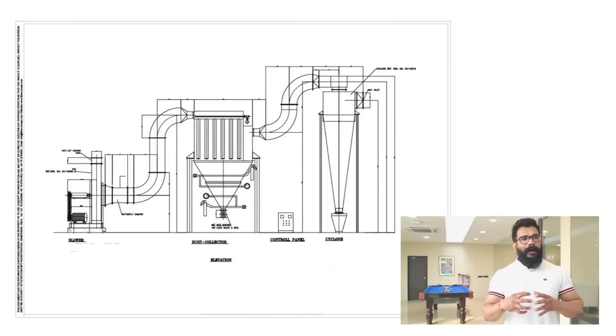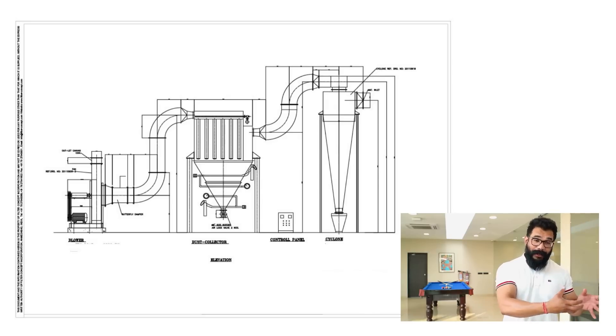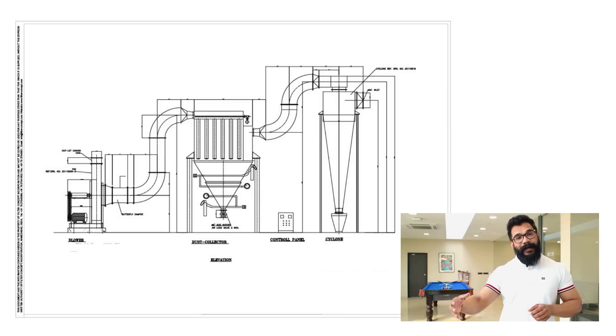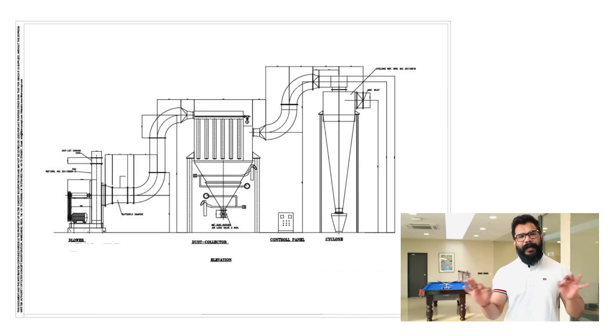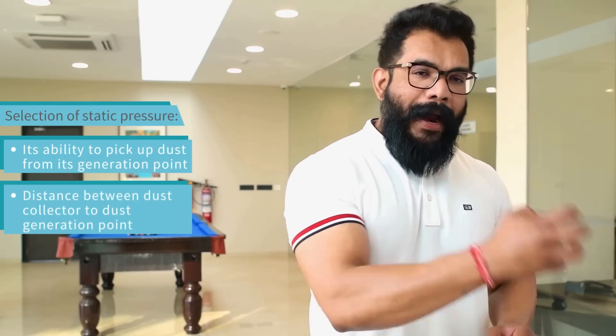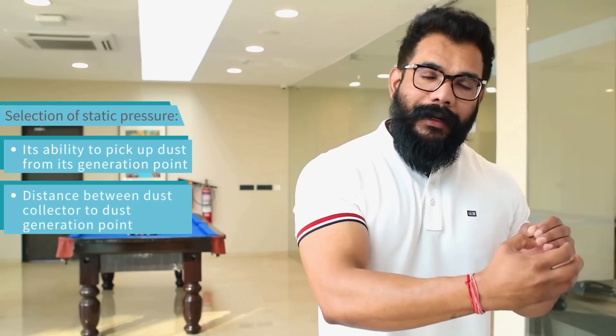Next is the static pressure available to us. I will try to share a general arrangement drawing of a dust collection system — how dust is generated, collected from its generation point, taken to the dust collector and blower, and finally released to the environment through a chimney. The static pressure must be adequate enough to handle the distance between the dust collector and the dust generation point.